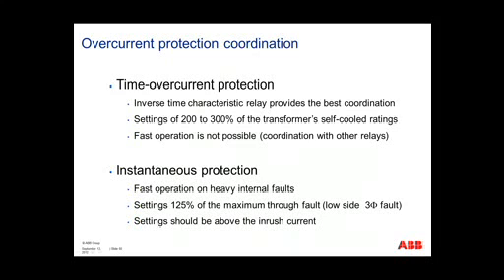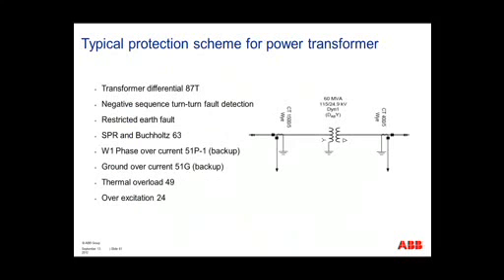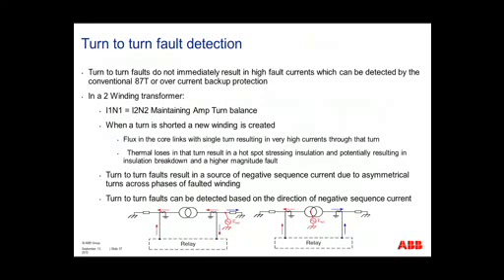Okay. The next one is, why is negative sequence used for turn-to-turn faults? The reason negative sequence is used for turn-to-turn faults is there is no other way to see these faults, since you cannot rely on your differential and your sudden pressure relay, because there is an imbalance in the turns ratio. So instead of having symmetrical, you have an asymmetrical component across those turns that, once you calculate the resulting vectors, you will see a negative sequence component to it. That is the solution, because previously we could not rely on the SPRs and the differential for picking up those kinds of faults.